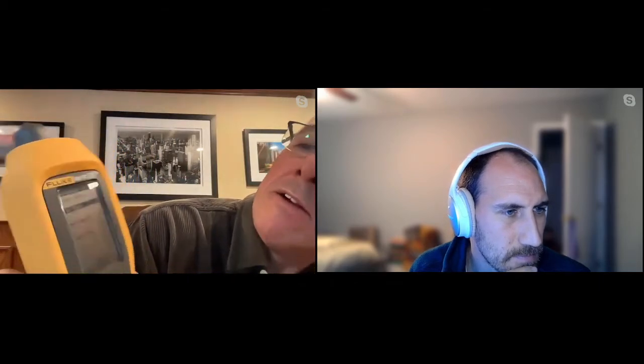That's right. What you'll notice, and I'll go in here into memory and view all setups. Can you see the screen? By name. And there are the pumps, all the pumps right there. So when we make a measurement and you hit save, you'll save to an existing machine or existing setup, it's called, and you'll select pump 1, 2, 3, or 4, or whatever, and save the measurement to the proper bearing location name, and then you're done, and then you can move to the next one.